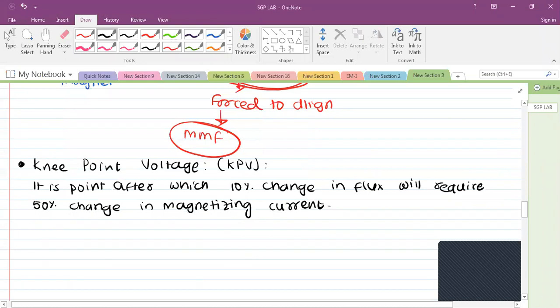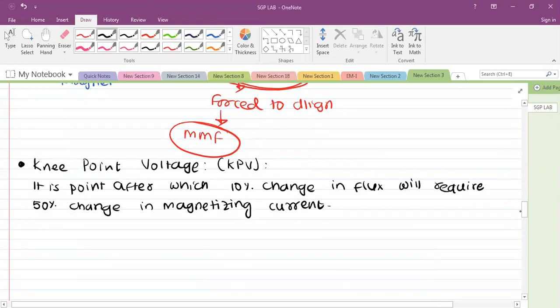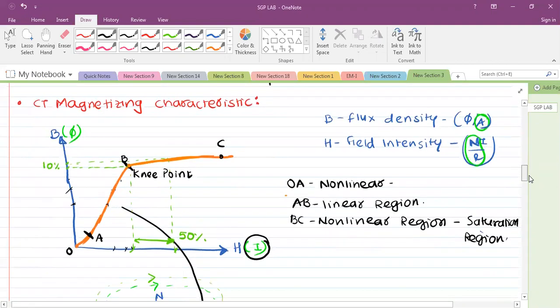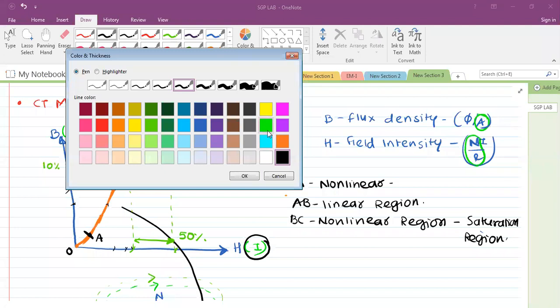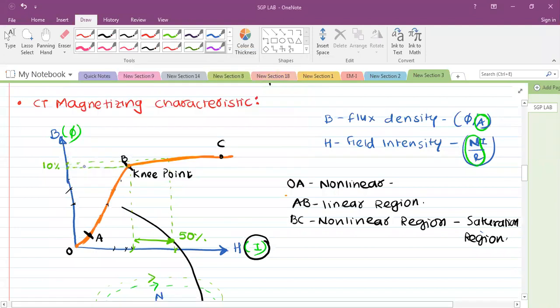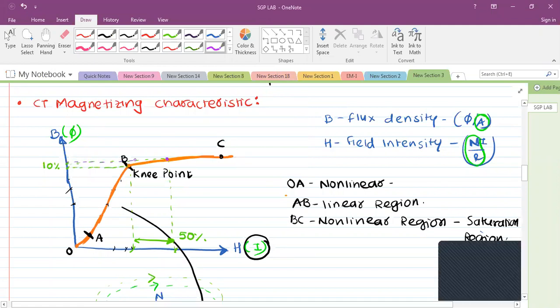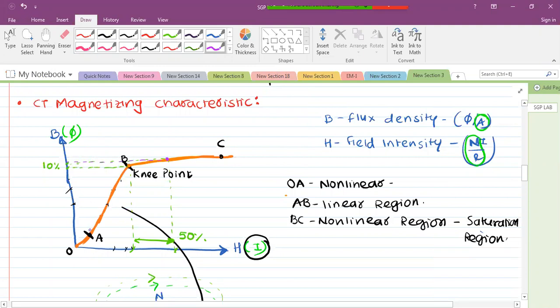That point is known as the knee point voltage on the saturation curve. And if you still keep on working your machine beyond this, let's say your operating flux density is right now at this point in the machine. Generally, machines are designed to operate in the region of A to B, whether it is a current transformer we are talking about right now or any other machine you have studied in your engineering. Generally, these machines are designed to operate within the range of A to B in the linear range.